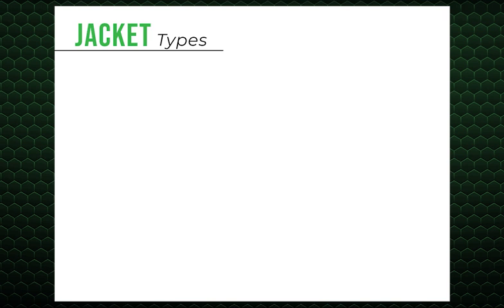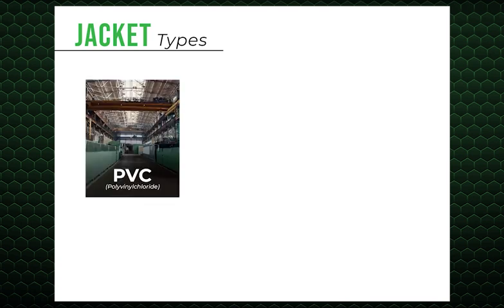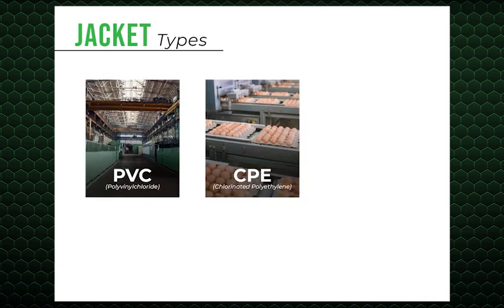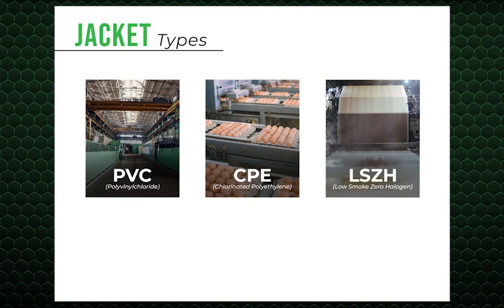Insulated conductors are available with an outer jacket for additional protection from potential mechanical damage, ingress of moisture, and chemical exposure. Service wire offers the following jacket types: PVC, CPE, and low smoke zero halogen. PVC is the most common jacket material. It is a cost-effective option. However, PVC cables come with the trade-off of not having the properties required for rugged environments.